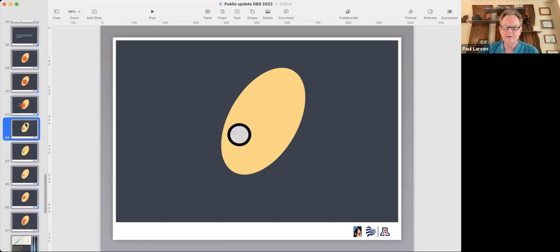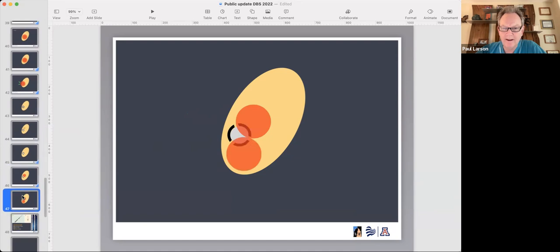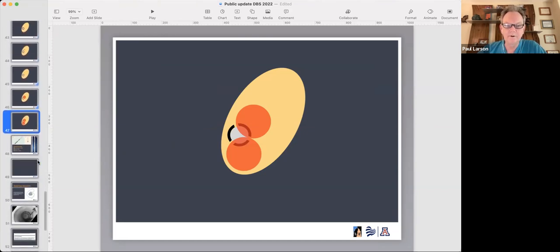So what Boston Scientific has done, and now the other companies have followed suit, is they've taken this ring and split it into 3 parts. So there are 3 stimulating surfaces. We call this a segmented lead. What it allows us to do is turn on one of these segments at a time. So you can just turn that segment and that segment on, and you can direct stimulation to the middle of the target, and you can leave this outer segment of the ring off. So you're not spreading stimulation outside the target. This is what we call lateral current steering. And it's really revolutionizing the way that we think about stimulating these targets.